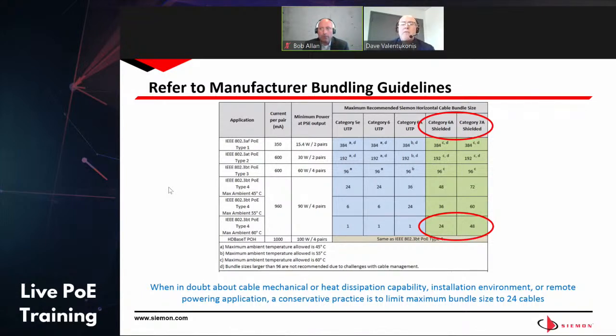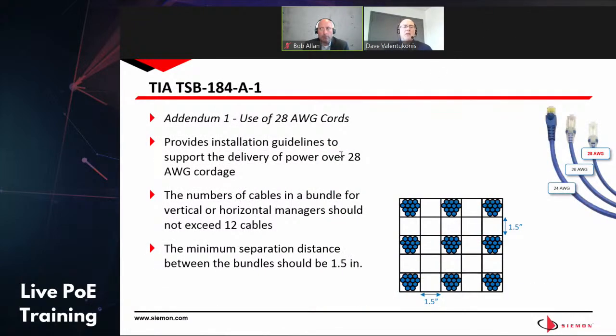As you can see, for category 6A shielded and category 7A, that magical number of 24 applies. Keeping those 24 cable bundles makes a lot of sense. Even if you look at type 4 with a maximum ambient temperature of 45 degrees C, which I think is suitable for many customers, you can get up to 24 cable bundles even with category 5E, 6, and 6A UTP as well. So that 24 is a good number. If you just don't know, it's a great general practice rule to apply across your designs, and then you don't have to have as much consideration for the rest of the installation.